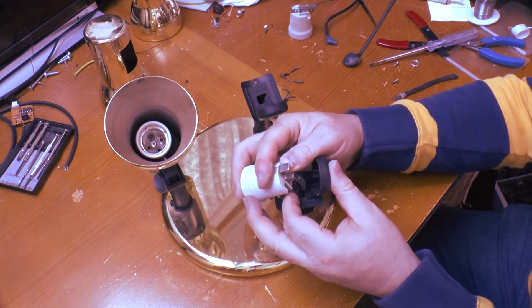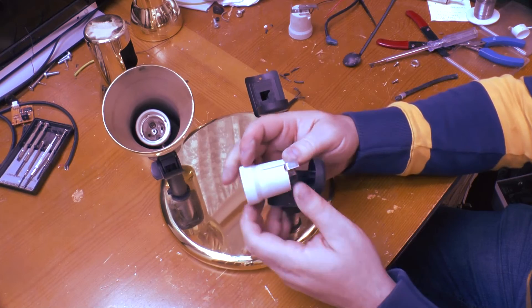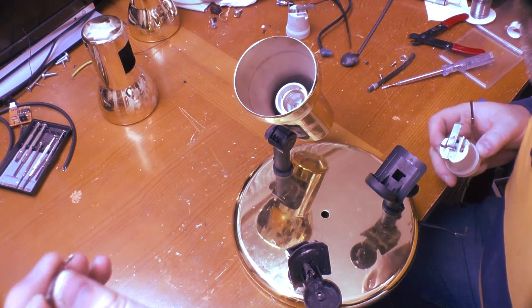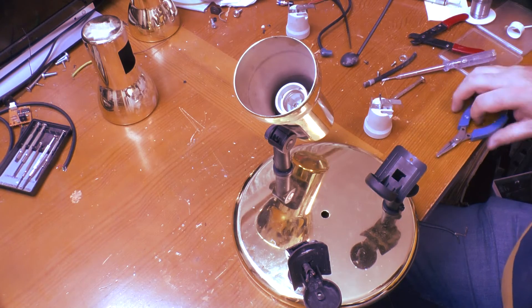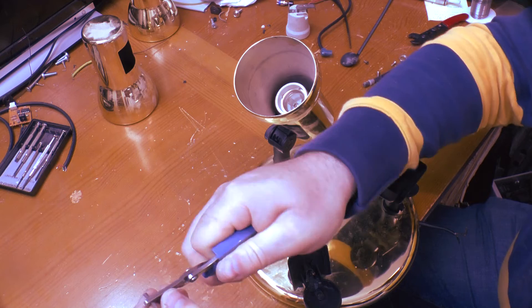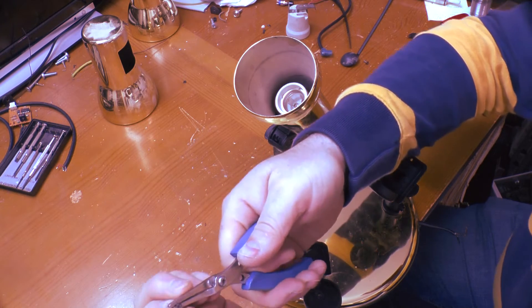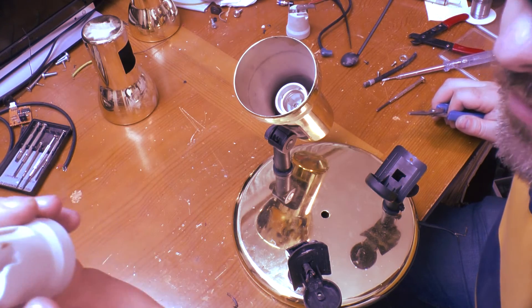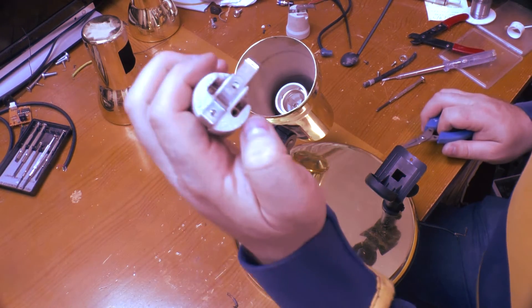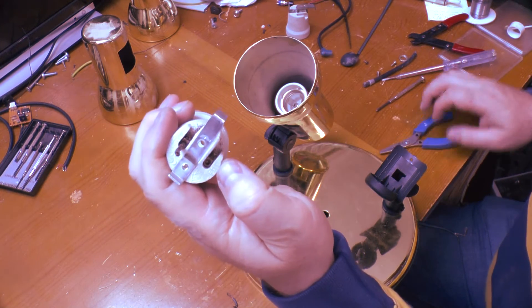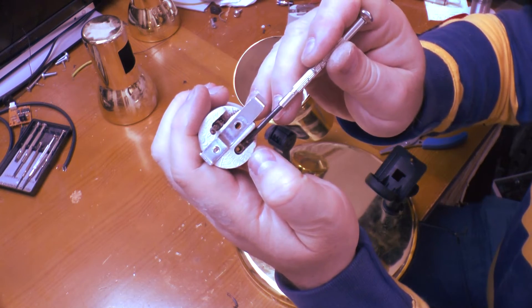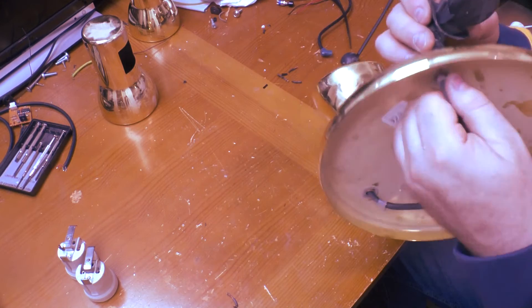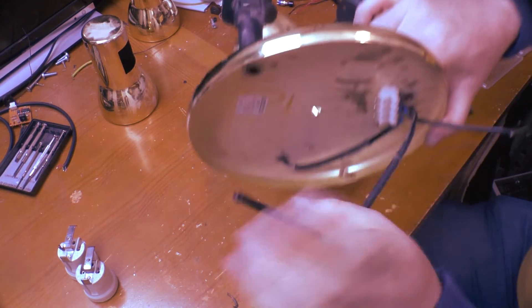This one's gone a bit easier. I know I've had to replace one of these sockets. You'll probably be able to see which one when I take it apart. Once again, the cables have gone very very brittle. Just cut it out. I've got one wire out. As you can see, this has also gone very dry and brittle. That's broken up there. The other one I can't get out because the head is rounded off on the screw. Something else of interest here. I don't know if you can see that terminal there. See that screw? I shouldn't be able to do that. I can feel that cracking in there as I was doing that. That's the screw.